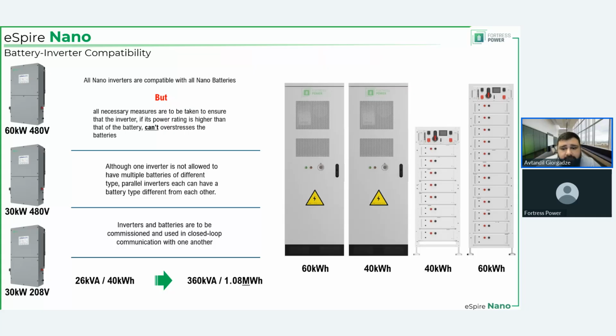Yes, it will go offline and separate from the inverter if overcurrent occurs, but relying on the safety mechanism is the same as relying on the guardrail rather than the steering wheel if you're driving a car, right? You don't want to do that over and over again. For grid-tied solutions with an undersized battery bank compared to the inverter, that's very straightforward. You just enter charge and discharge limits appropriately so that the battery is not overcharged. If you have load, there must be a hardware guarantee, a breaker of some sort, or a fuse for that matter, so that whatever the battery can output, the load cannot demand more than that.